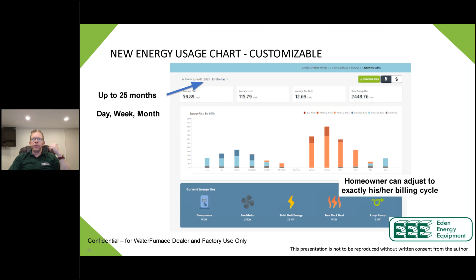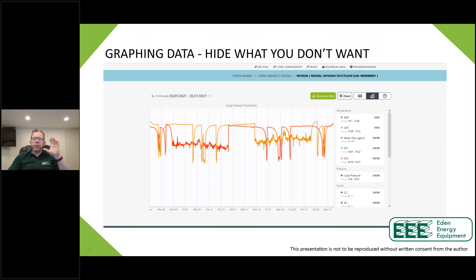And here's a look at the graph data view. So for example, if we had a freeze protection lockout, we could pull up the graphical view, look at just loop freeze protection, and see that, okay, there are significant swings happening with the entering water temperature. So sometimes you'll use the graphical view, sometimes the Excel view, and sometimes the troubleshooting view—it's truly up to you.